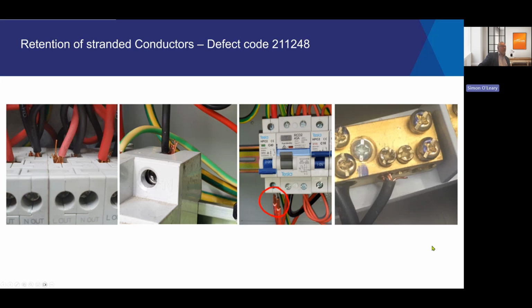Lastly, I'll just talk about another common defect we see, where cables aren't correctly terminated in things like circuit breakers and neutral and earth bars. The wiring rules say that circuit cables, particularly copper, stranded and flex conductors, need to ensure that the strands don't come out of the terminal. And there's often a lot of discussion around should this be done using ferrules or bootlaces. The wiring rules don't specifically ask for those to be used when terminating, but they do talk about strands not escaping the terminal.